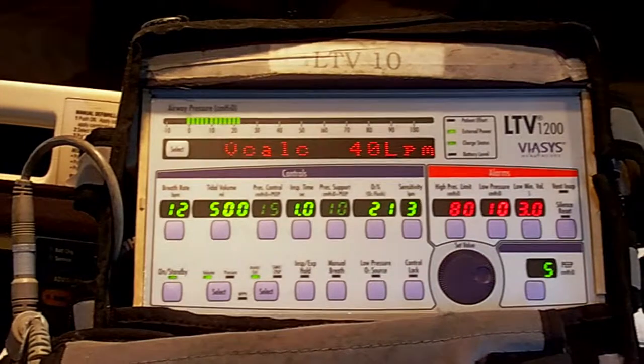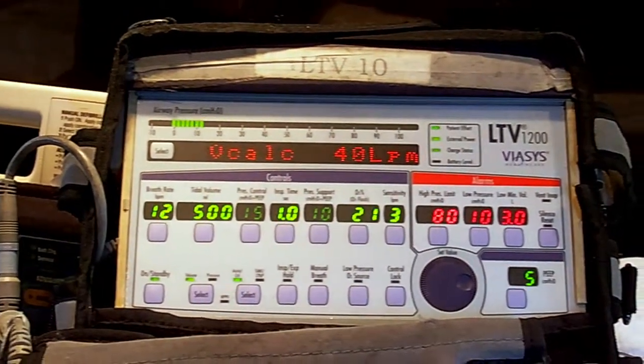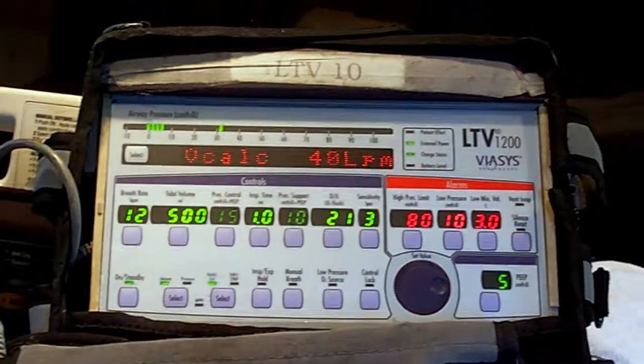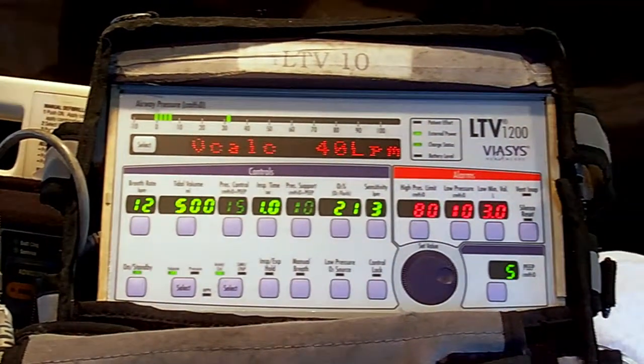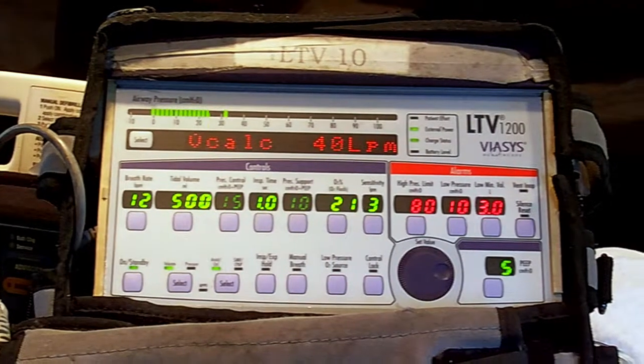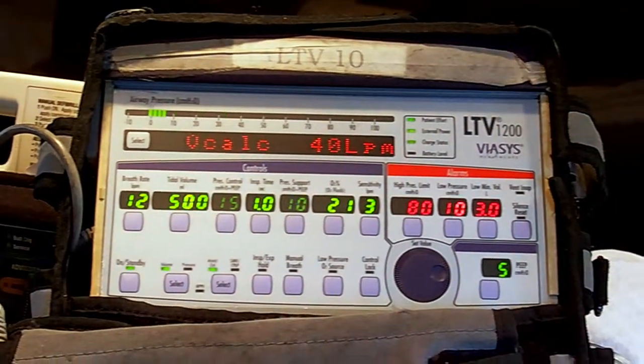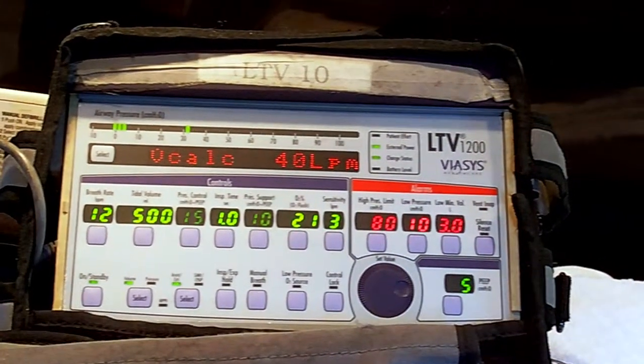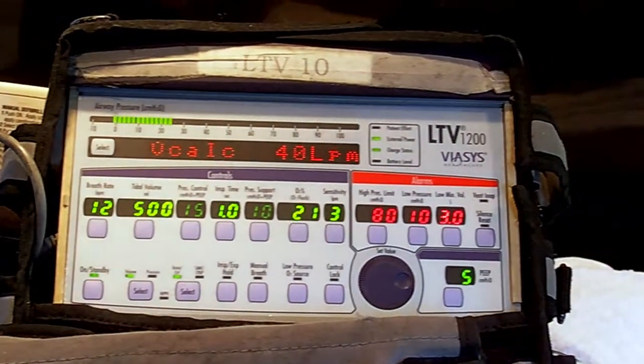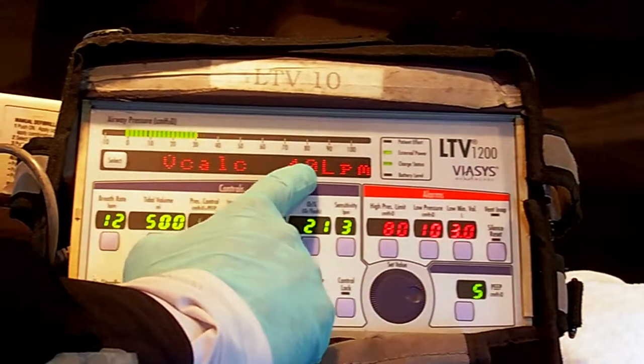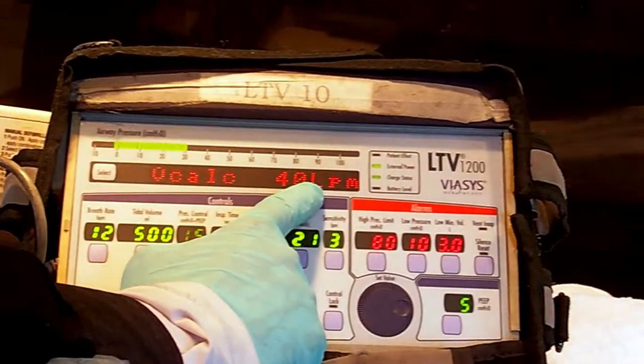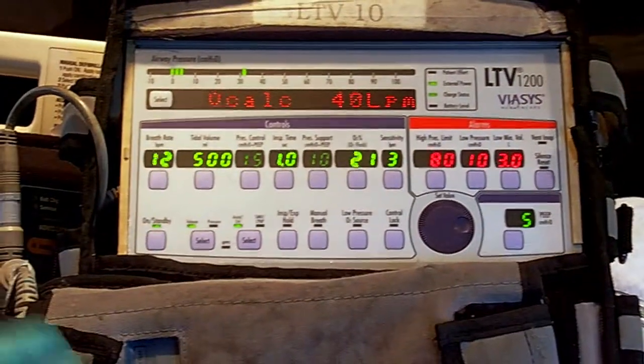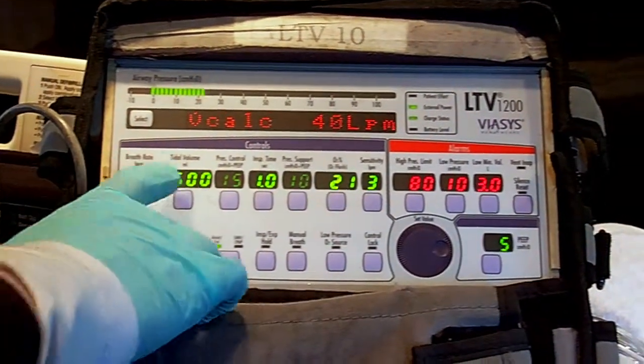The next breath type is volume assist. The trigger is patient effort — what triggers the ventilator is the patient sucking on the tube with negative inspiratory force, which drops the pressure and drops the flow. Target is once again flow at 40 liters per minute. And cycle, which tells the ventilator to stop inflow of gas, will be tidal volume.